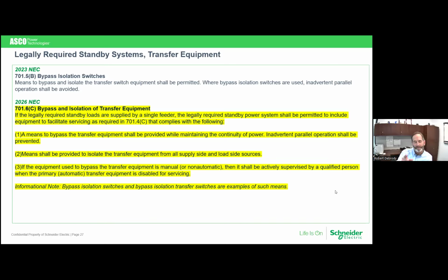Even though 2020 was the first time a provision like this appeared in the code, mandating bypass switches in a critical operations power system, for over 40 years you can look back and find no hospitals built that don't utilize a bypass isolation transfer switch. So this was the code catching up to what industry has already known, that you've got to have a way to get around that transfer switch if it fails.